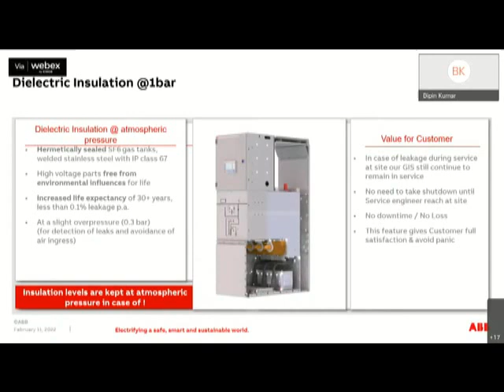We also give, because GIS is a maintenance free product, but then you can also have a repair opening in case something happens, because products are always designed to handle the worst circumstances. But then yes, as a design feature, this is also available. Once we have taken the bus outside the switchgear, then we can take any intermediate panel.